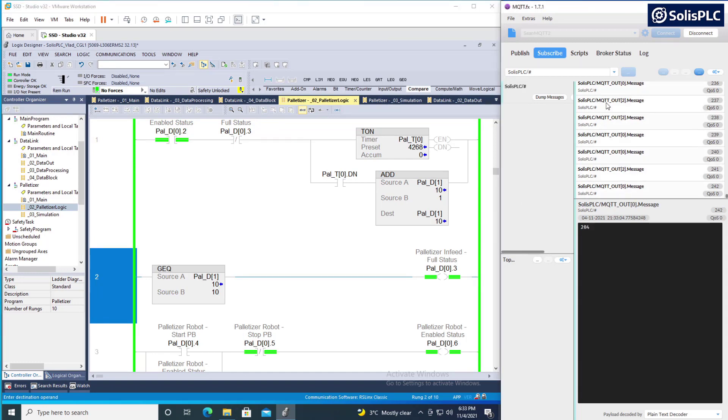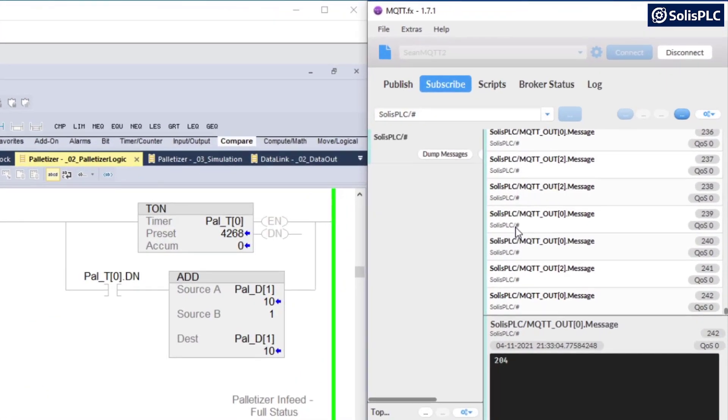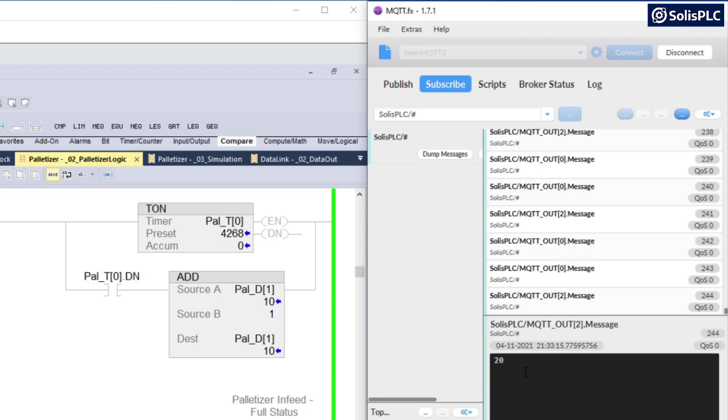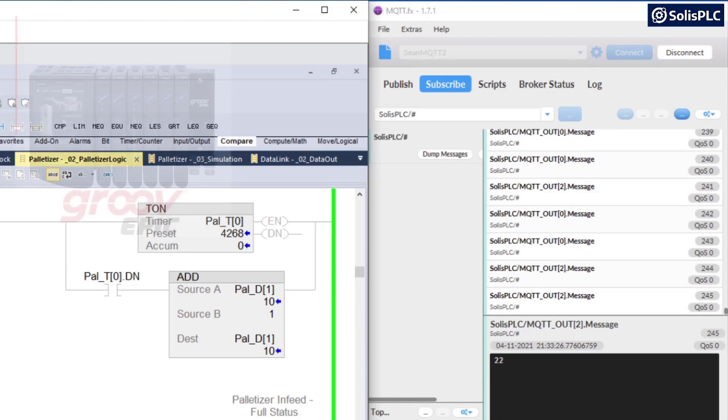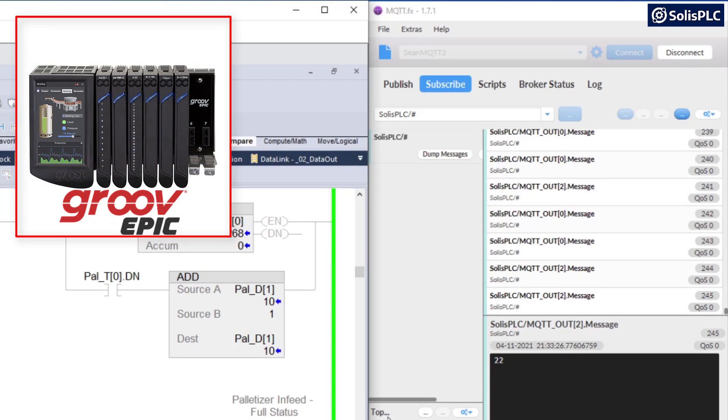Let's take a quick break and look at the MQTT.fx window that has been shown here the entire video and that I haven't really explained. So what's happening here is that I'm reading the messages that are being received on the broker side. And you'll notice that the variables are changing from 20 to 22 to 24. So it's incrementing the number of packages sitting inside of my palletizer and it's sending that data to the broker. So what's happening in the background, what you cannot see is that this Allen Bradley PLC that's sitting behind me is actually communicating through Ethernet IP to an Opto 22 controller and that controller is sending MQTT messages to the broker.